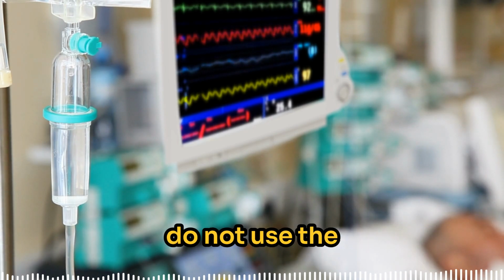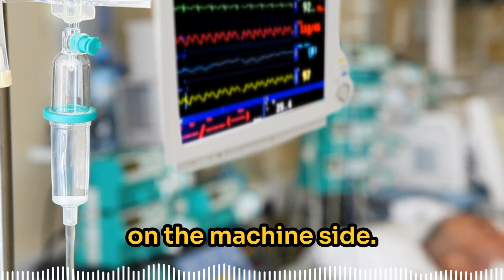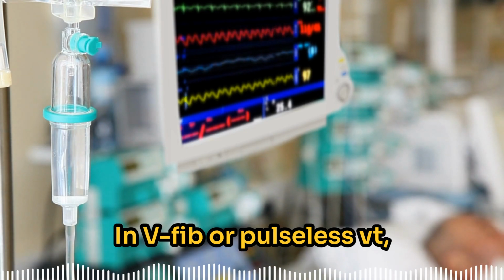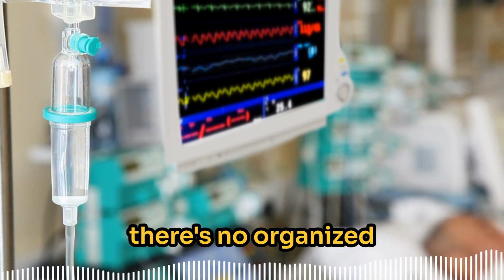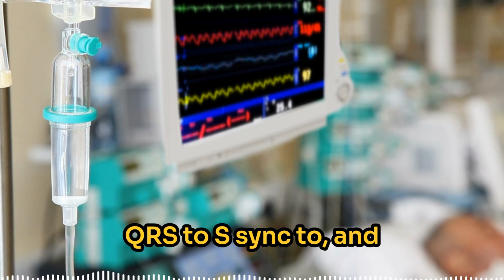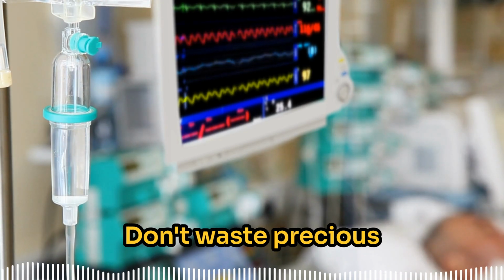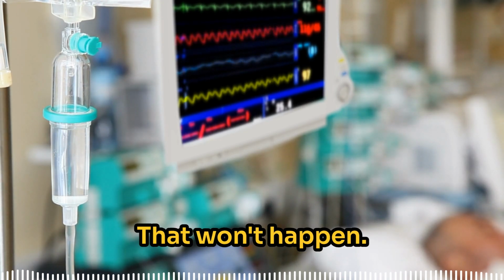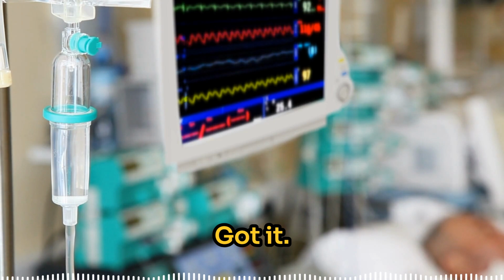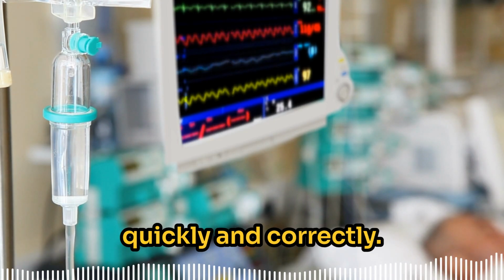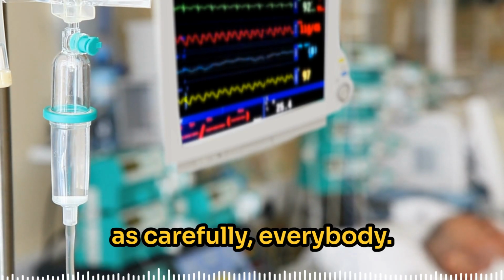And the sync button? Do not use the sync button. This is the key difference on the machine side. In VFib, or pulseless VT, there's no organized QRS to sync to, and you need to deliver that shock immediately. Don't waste precious seconds waiting for synchronization. That won't happen. No sync for defib. Got it. What else? Apply gel or pads quickly and correctly. Clear the patient just as carefully.